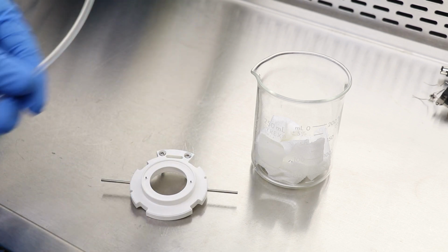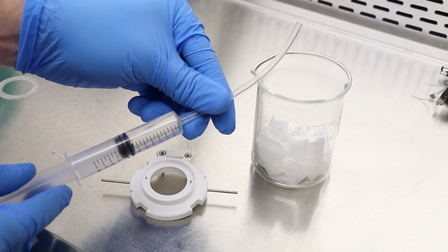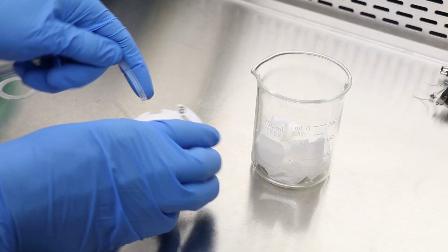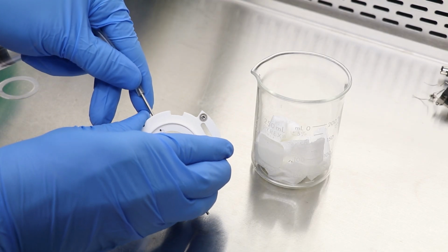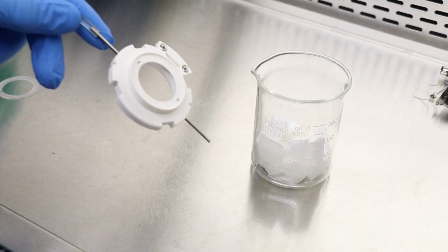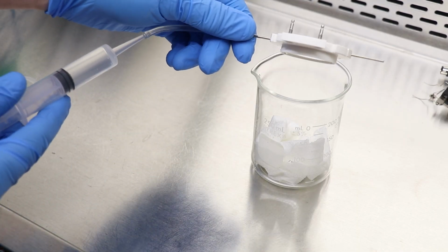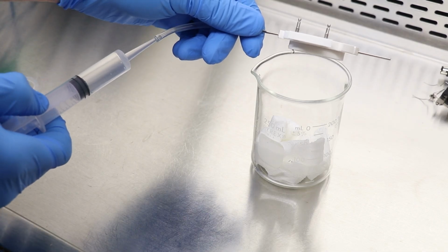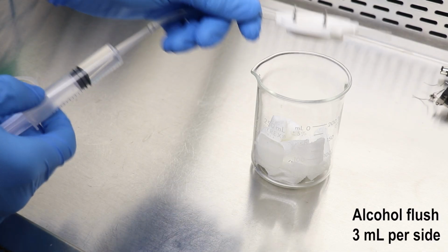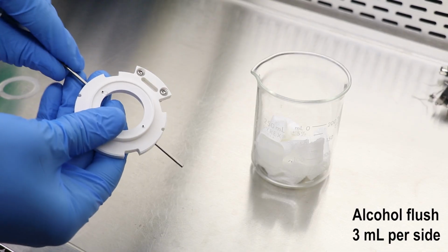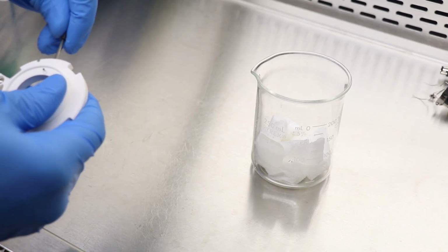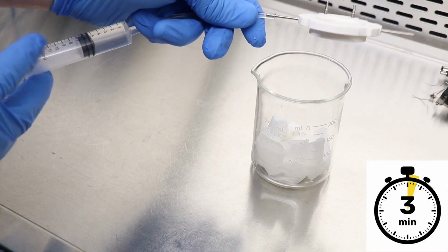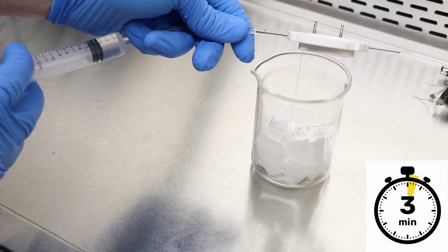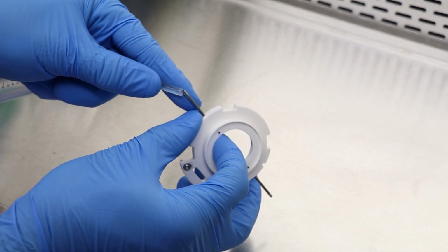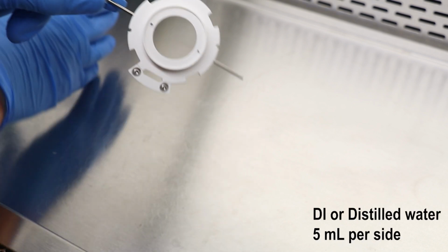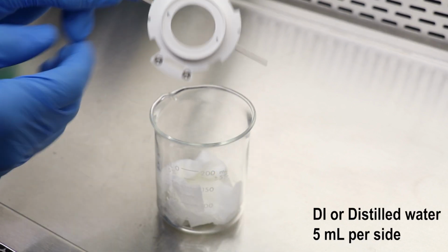Use a syringe with alcohol, then begin flushing the chamber perfusion ports. Left side and right side independently. We suggest 3 mL minimum per side to flush. Let alcohol sit inside the top for 3 minutes for initial sterilization. Flush with 5 mL minimum of deionized or distilled water per side.